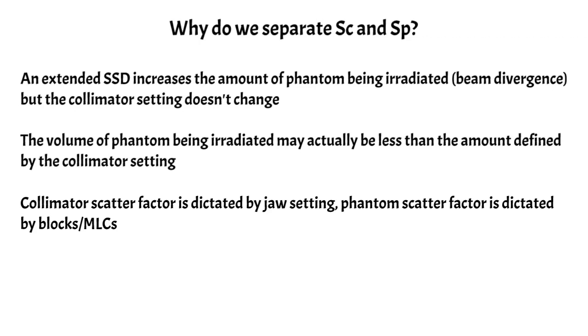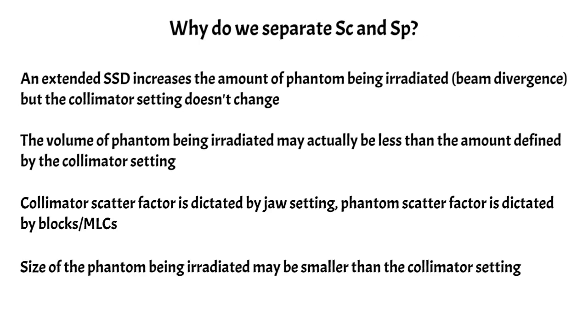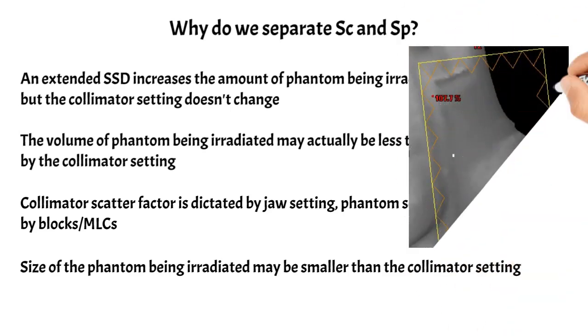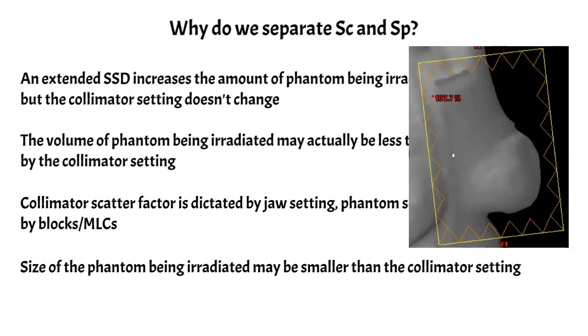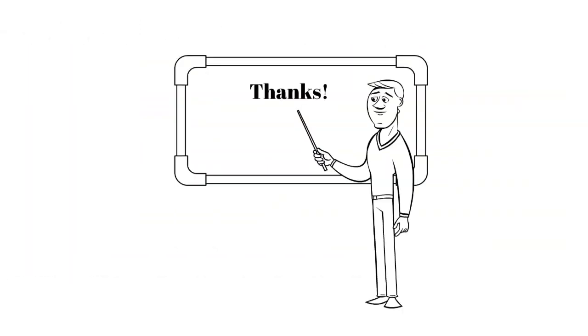Another instance where the field sizes differ is when the size of the phantom being irradiated is smaller than the actual collimator setting. An example is a breast tangent field — you can see that there is really only tissue in part of the field, in which case you would only use the size of that tissue in the field for your phantom scatter factor. This is another example of why we need to separate these two factors. And that's all I have on scatter factors — I will see you in the next video.